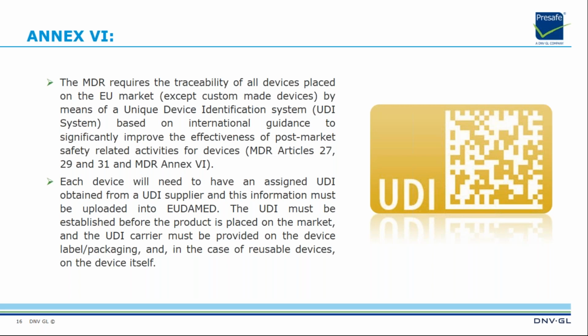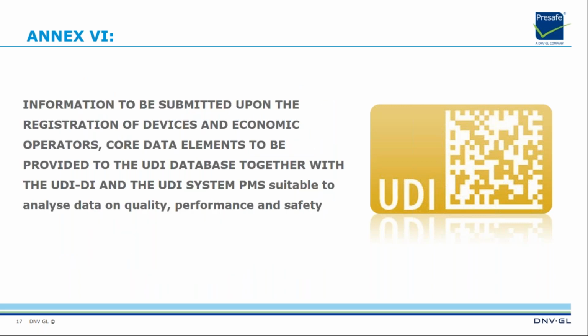It must be considered. Each device will need to have an assigned UDI obtained from a UDI supplier, and this information must be uploaded into EUDAMED, which means European Databank on Medical Devices. The UDI must be established before the product is placed on the market, and the UDI carrier must be provided on the device label, packaging, and in the case of reusable devices, on the device itself.